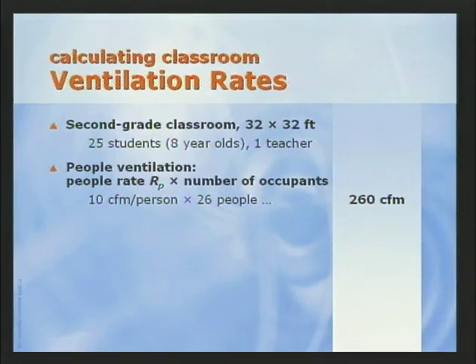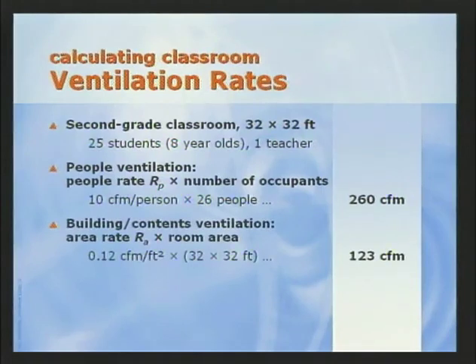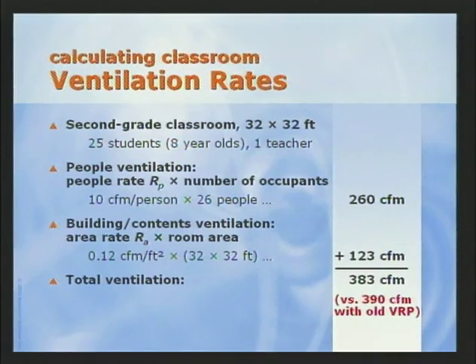To determine the building and contents component, the area rate per square foot of 0.12 is multiplied by the area of the room. This requires an additional 123 CFM of outdoor air for the classroom to handle the building-generated contaminants. The total amount of outdoor air required for this classroom is 383 CFM. Now, in comparison, using the previous version of the ventilation rate procedure, we would have taken 15 CFM per person times the 26 people for a total of 390 CFM. As you can see, in this case, the ventilation rate is essentially the same for both procedures.